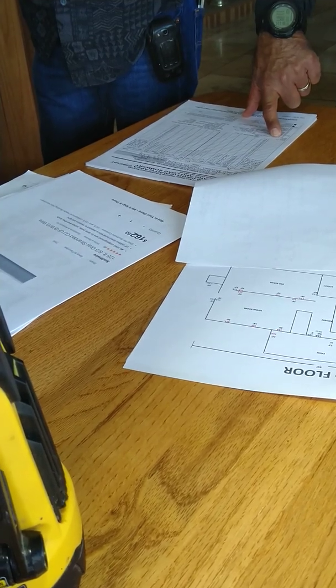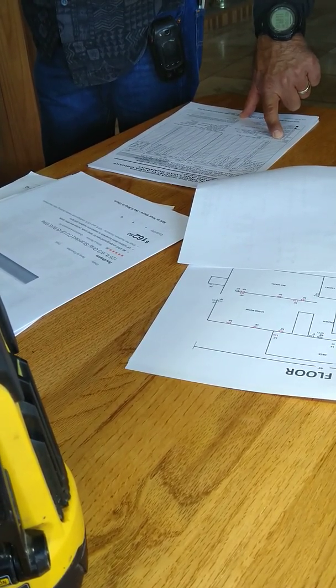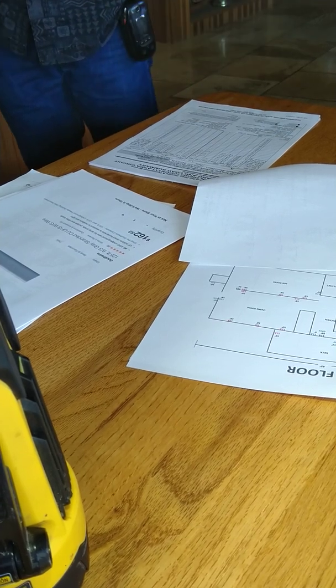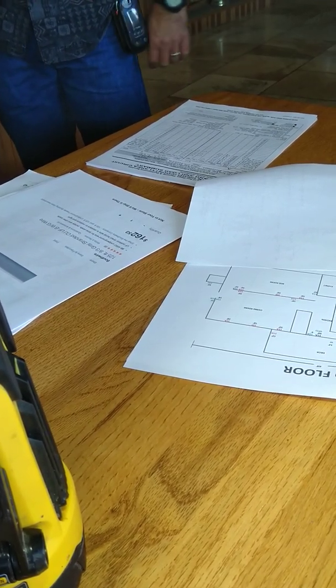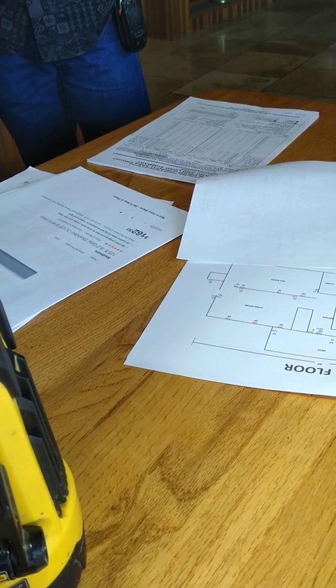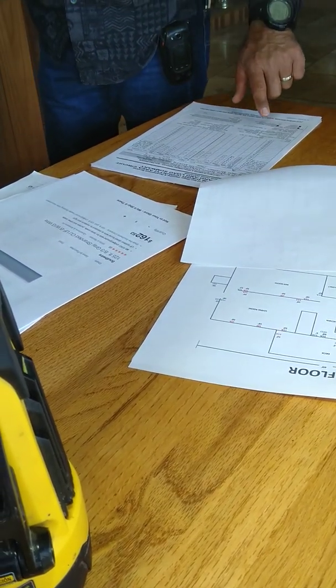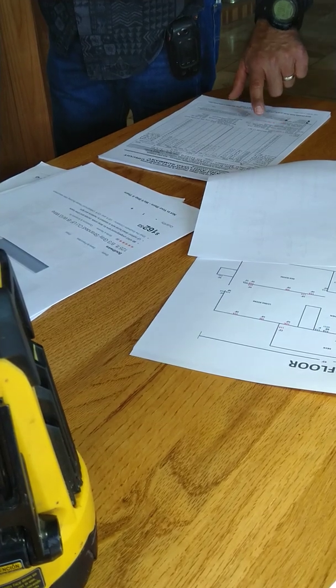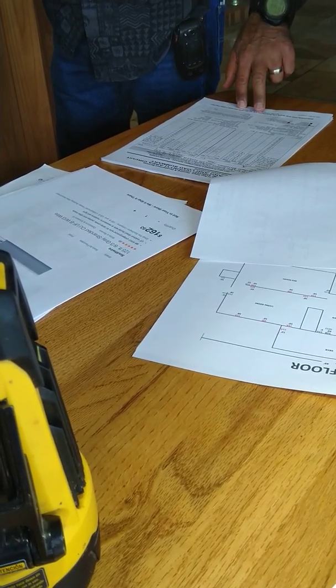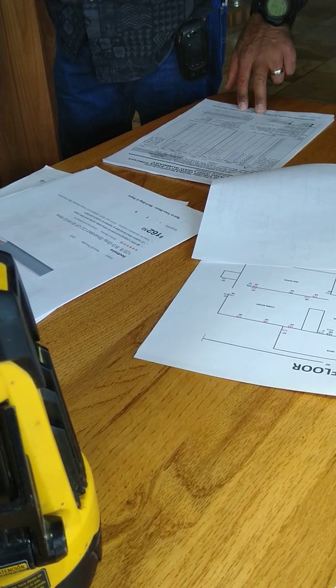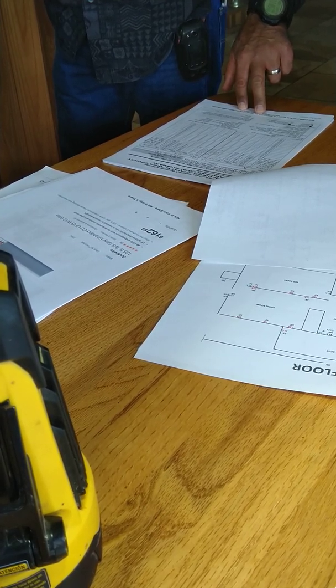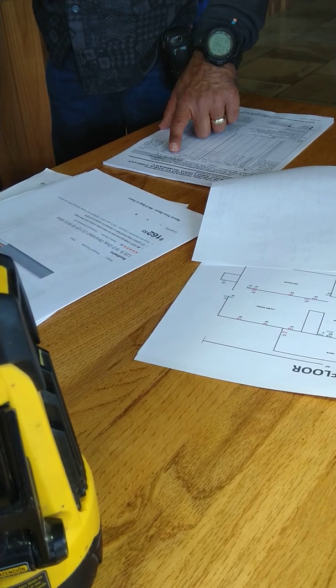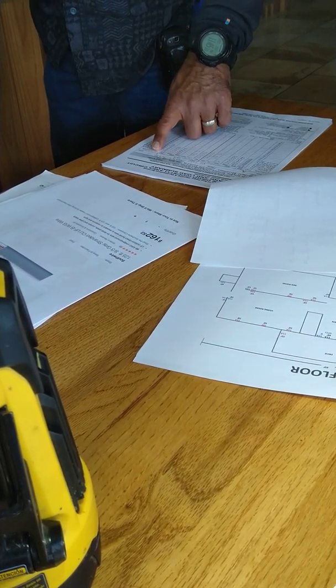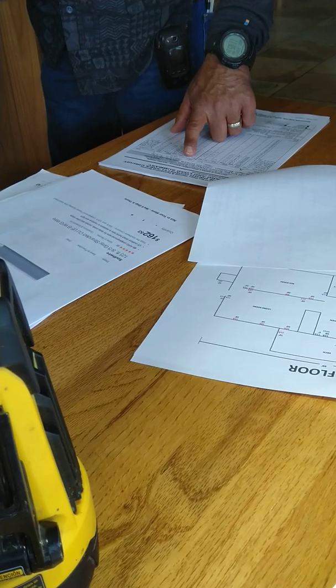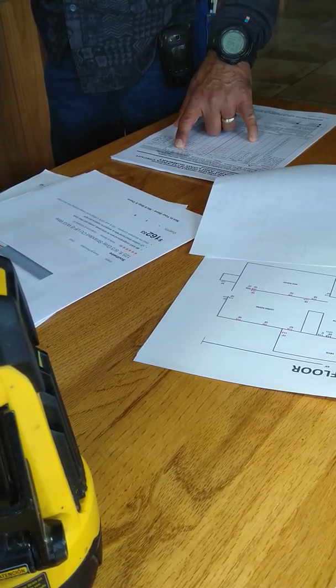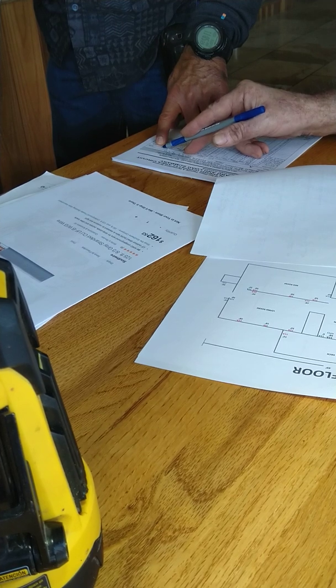When you open up this sub panel, you're going to find that it'll say bus panel of 100 amps or 60 amps or 30 amps. That'll tell you what that box is designed for. Then you're going to have, let's see here. It doesn't show where the load would be placed. This would be the wire size, this is the wire going to the box.